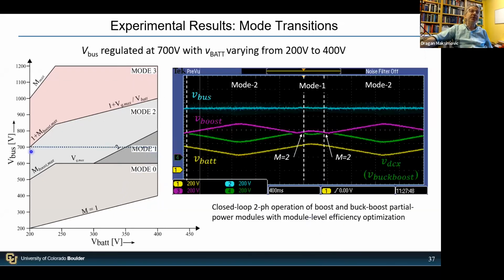Here's an example, going horizontally between modes 2 and 1. The bus voltage is maintained, and you don't see any disturbance in it. As the battery voltage increases from 200 to 400 volts, the boost voltage goes up and down, the buck-boost voltage goes down and up, and the combination of the two results in an output voltage that doesn't change.